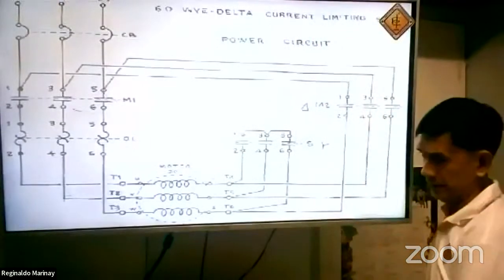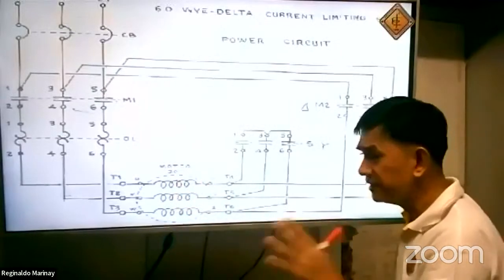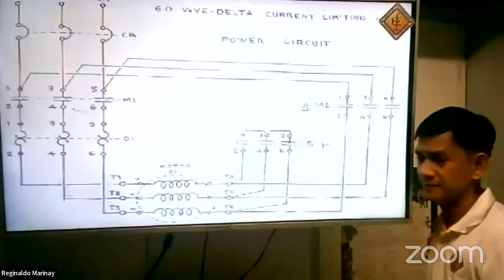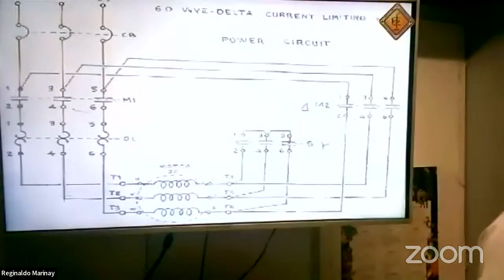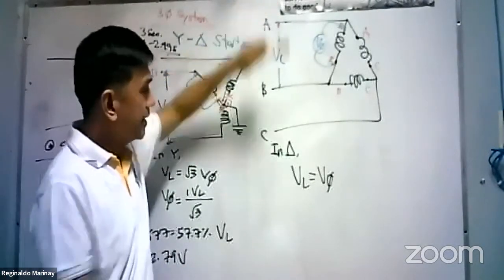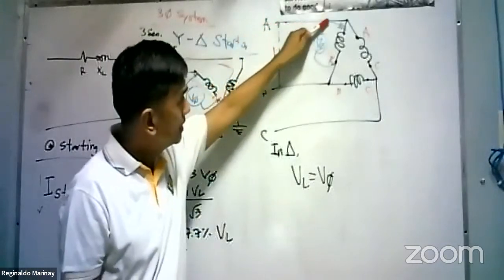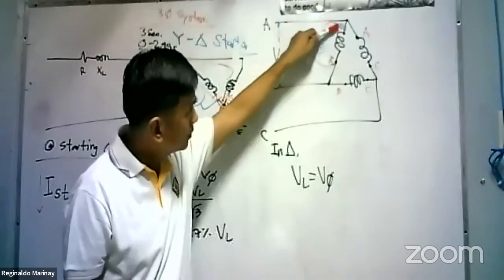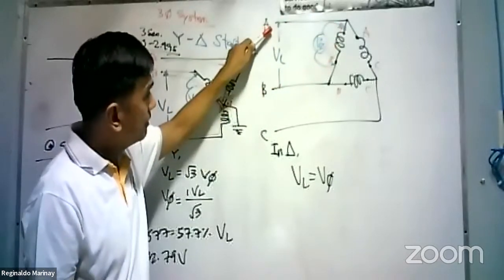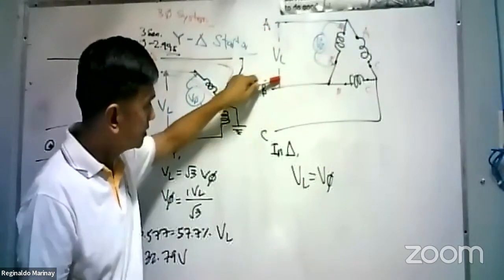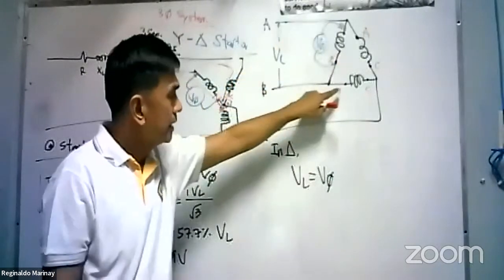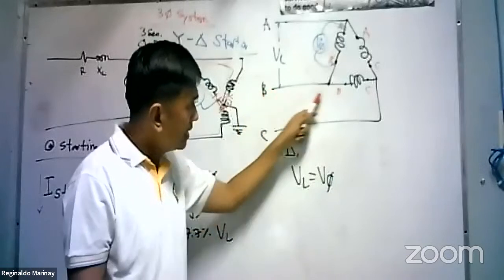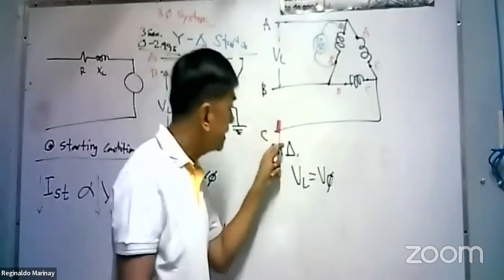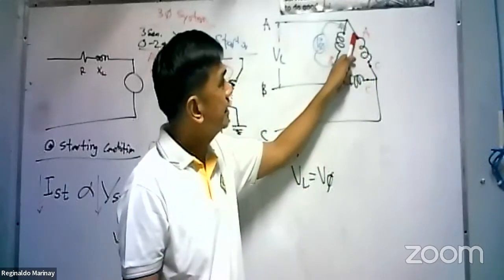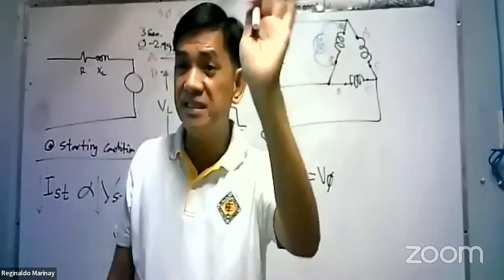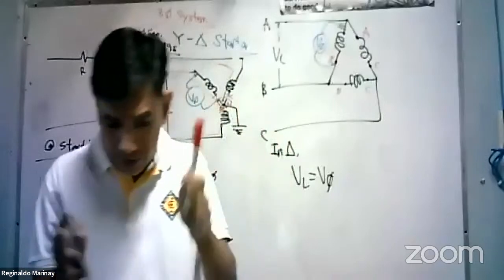Now, what is the proof that these 3 windings are now connected in delta? It's not anymore Y. What is the proof then? Take a look here for the basic principle. Remember that the current will flow from A to the coil, and then going to B. Let's say the flow of current is from A to B. This coil, BC, the current will flow from B going to C. And then from C, the current will flow going to A. So that is simply AB, BC, CA.